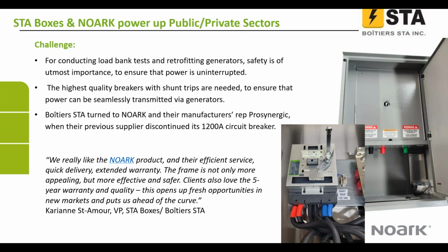So what are STA boxes? They are permanently installed boxes designed for temporary connections. We use the Cam-Lok connector as an oversized power outlet to connect generators, load banks, or even event equipment. They're really easy to use, weatherproof, and resistant to cold temperatures. Also, our enclosures integrate NOARK's components, such as molded case circuit breakers, which are available in various amperage, voltage, and short circuit current ratings.